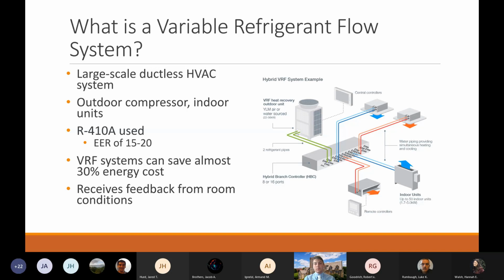This is important because we wanted to make the building as efficient as possible, so the refrigerant choice was key. The variable refrigerant flow system can save almost 30% in energy costs, which is huge given our efficiency goals. It's so efficient because it receives feedback from each room individually and cools based on the room's needs, slowing down or speeding up its compressor accordingly.